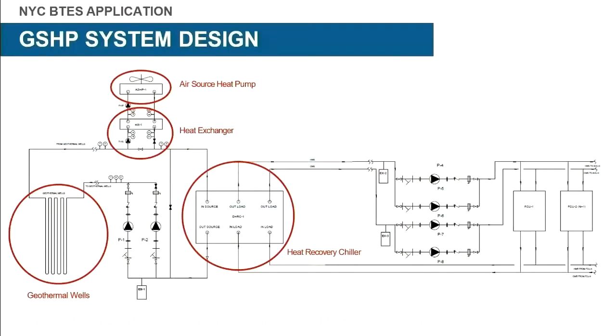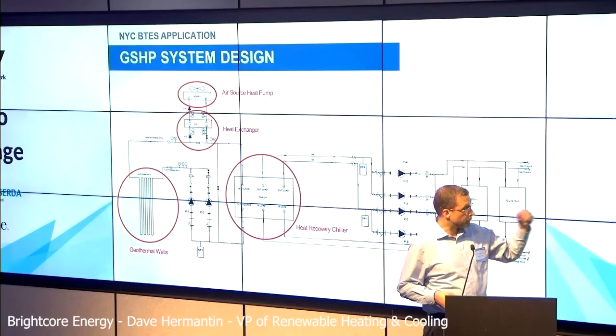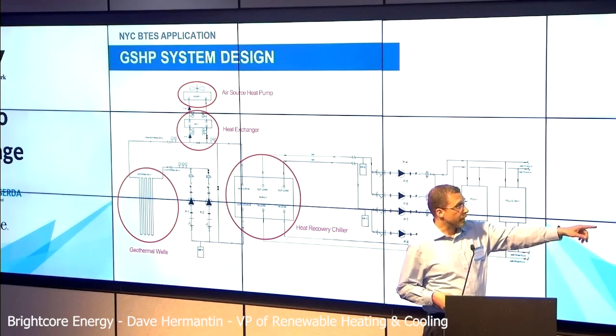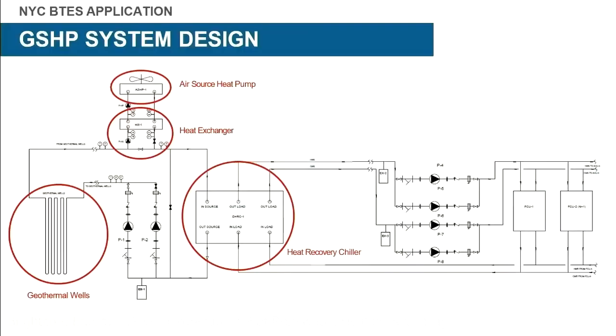There's a lot of talk about how systems and buildings need to be reconfigured to be able to electrify. This type of configuration is utilizing a heat recovery chiller. And this heat recovery chiller is providing heated and chilled water to fan coil units throughout the building's lobbies and offices and some other accessory spaces. What's different is what's on the source side, on the left-hand side. So on the left-hand side, you'll see geothermal wells that are circled on the lower left-hand corner of this, and an air source heat pump that's on the upper side of the graphic.